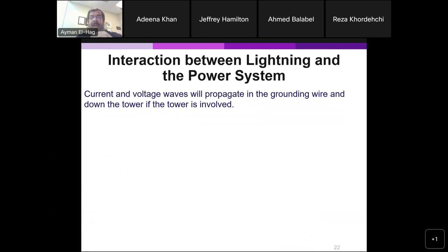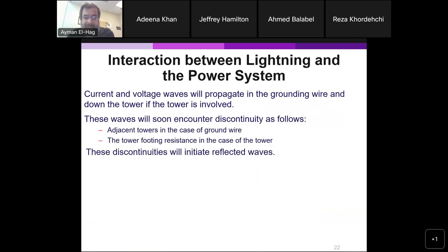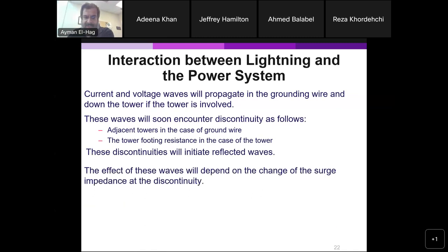Now the current and the voltage wave will propagate in the ground wire and down the tower if the tower is involved. It depends where it hits, and this is completely random. We have no control over where the lightning will hit. These waves will encounter a discontinuity, as we mentioned before. This could be an adjacent tower or the tower footing resistance. So the lightning hits, it goes to another tower or to the foot resistance, and this will initiate the reflected waves, as we mentioned in the beginning.